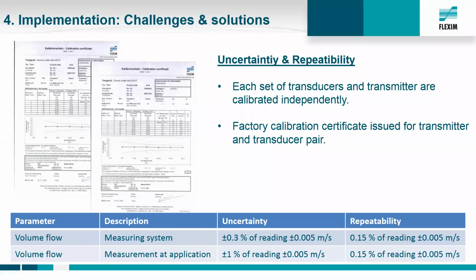So what we are doing is we are calibrating our systems in the factory, and here we have a modular approach so that we are calibrating our transmitters and transducers independently, and each of these parts gets a calibration certificate so that you can use each part, and for example replace a transducer pair or a transmitter, and you still have a calibrated system or calibrated loop.